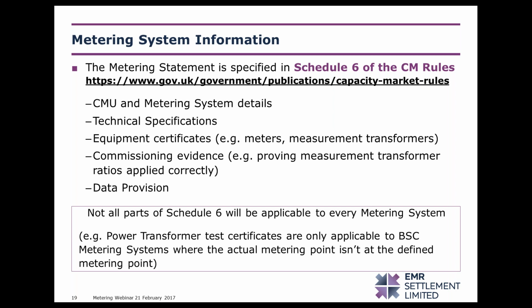Please be aware that Schedule 6 was designed to cover all aspects of every metering configuration solution, so not everything will be applicable to your metering system. If something is not applicable, the metering statement should state that this is not applicable. This is to prevent EMRS having to contact you to clarify whether you have completely filled in the metering statement. Typically, a metering statement will list every section of the Schedule 6, from A to R, and then will provide either an answer in that section or will specify a link to an attachment that is used as evidence for compliance with that section. So where you have evidence of meter test certificates in a separate attachment, section L of the metering statement would refer to those separate attachments.